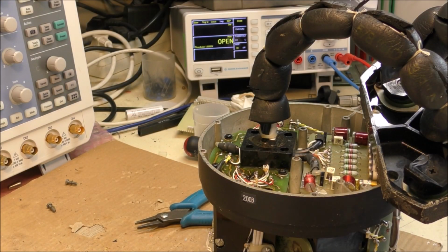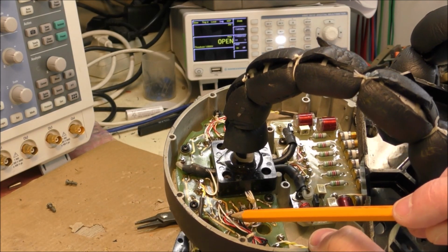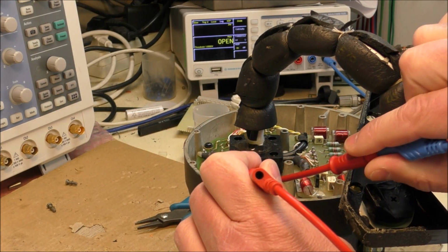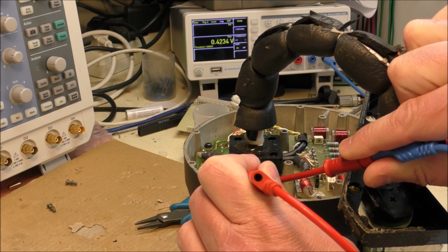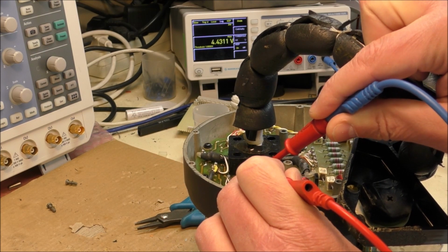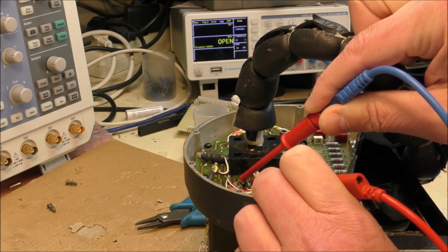I have found that one photodiode here is left open, and effectively the photodiodes are connected on that plate here. There is one common point, which is a black wire, which is connected to the ground, and the anodes of the photodiodes correspond to the red wires, this one, and this one. And we can see that effectively one is left open. So we can see that this one has a direct voltage of 0.42 volts approximately. This one also 0.38, but the last one is left open.